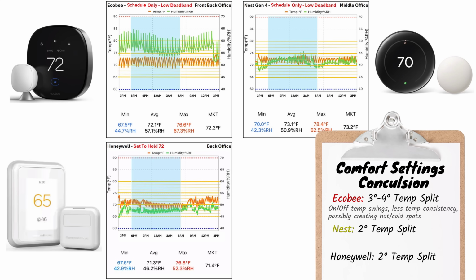If you're operating a single-stage system on a 2 degree split, it's obviously going to make the system cycle on and off a lot more frequently, which will wear out the equipment faster. No manufacturer would look at this graph for the Honeywell and Nest and say that's good for the equipment.